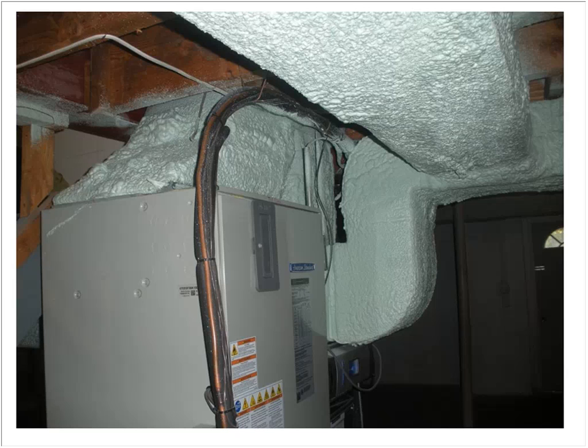And I think that they're overcompensating here for poor duct design. That trunk coming off a secondary trunk and the truncated plenum on the top of that furnace are examples of poor design, and they're compensating. But the purpose of the slide is to show you that you can air seal these if you don't want to go through and paint every joint with a Class 1 fire rated material that's suitable for duct sealing.